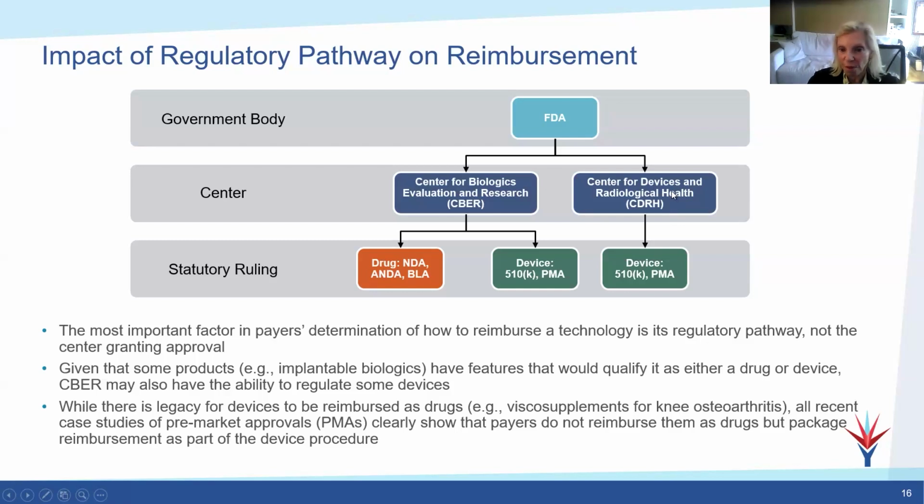It's the regulatory pathway. So perhaps you've heard talk of 510Ks or de novo pathways. 510K is if your technology is substantially similar to what's already available. It doesn't mean that you'll need no clinical evidence, but probably very little clinical evidence because the innovator has already provided the clinical evidence. It takes much longer often to get a de novo designation for your regulatory approval. But it may be worthwhile because your reimbursement may be higher using a de novo pathway.